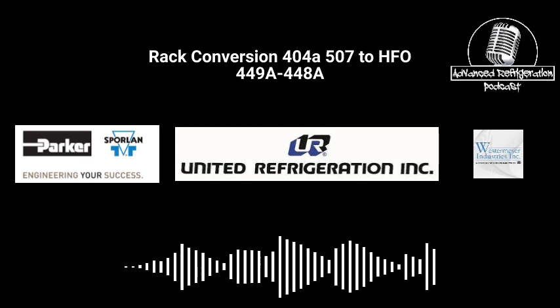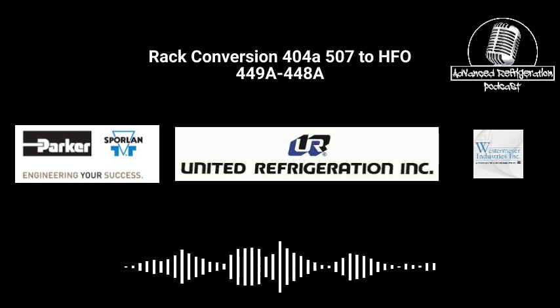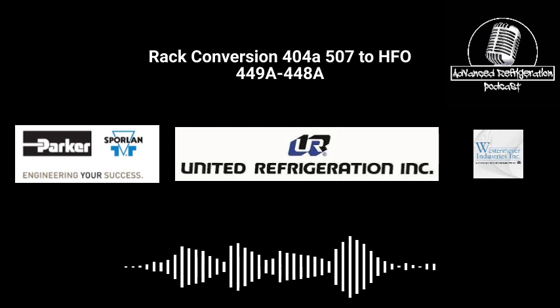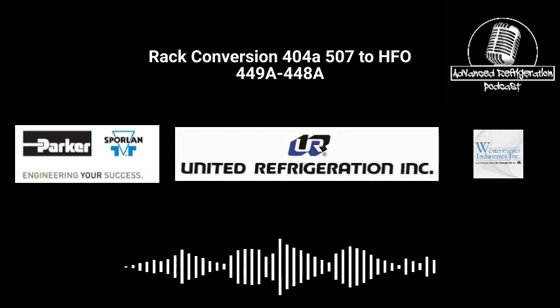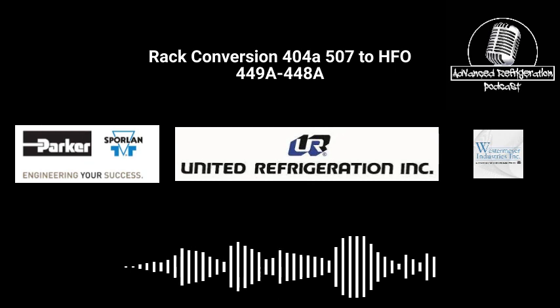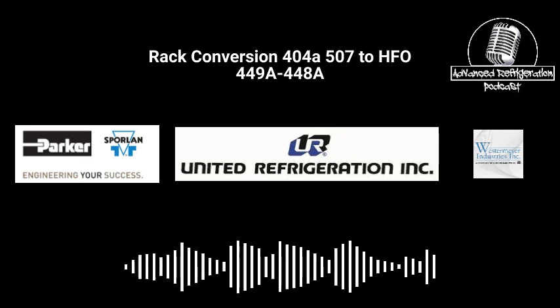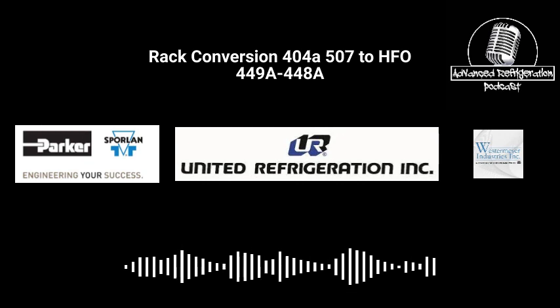So before you start drilling holes in the panel, take this from experience, make sure the panel's going to close and you aren't going to hit anything. You look at the depth and think it'll be fine, plenty deep enough, but then it's hitting a breaker, or now it's hitting the back of a board. In my case, somebody put one in, shut the door, and the wire just arced to the board.